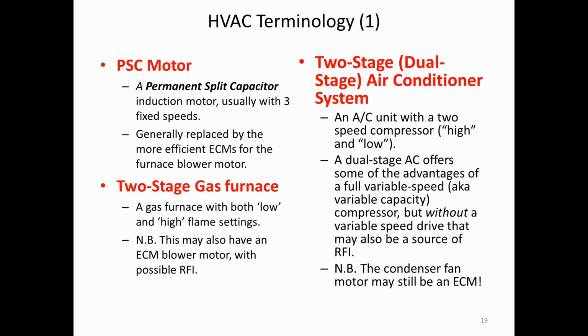A 2-stage dual-stage air conditioner is an entirely different matter. That means it has a 2-speed air compressor with high speed and low speed. It has some of the advantages of a full variable speed compressor, but without a variable speed drive, that can be a source of RFI. And remember, a variable speed drive is almost the same as an ECM. It's just it produces 3-phase AC rather than 3-phase DC.